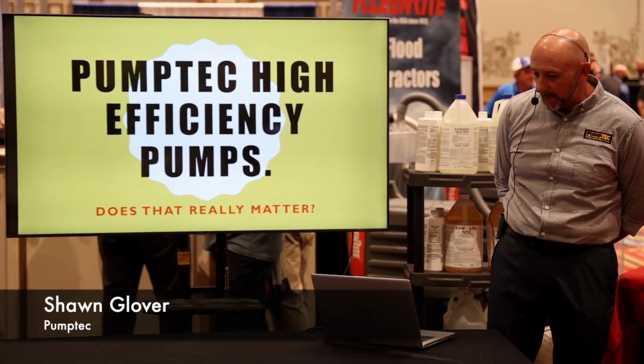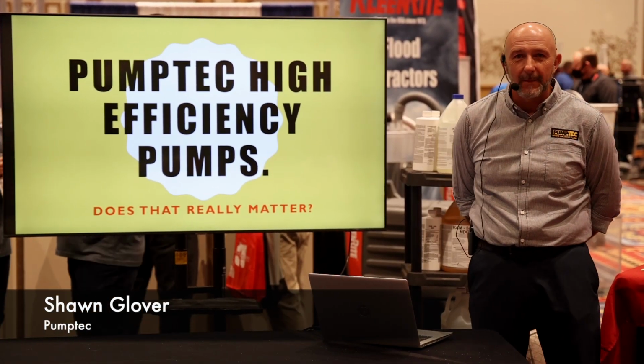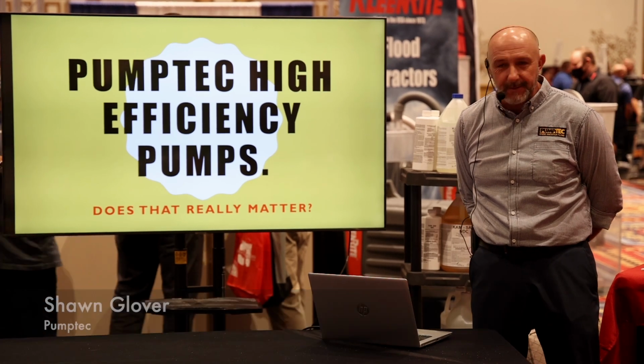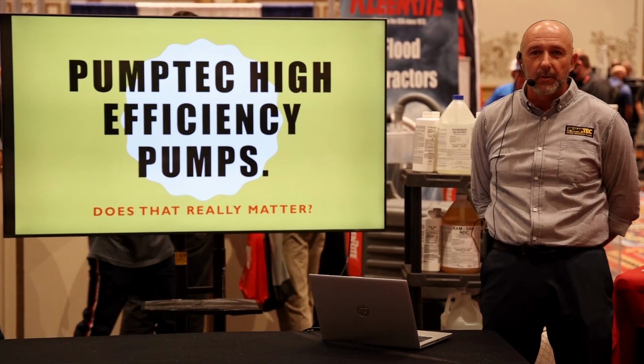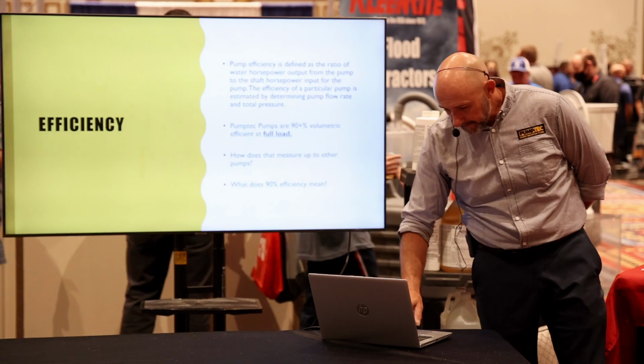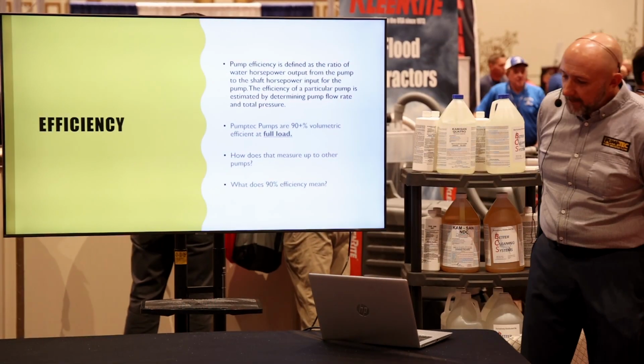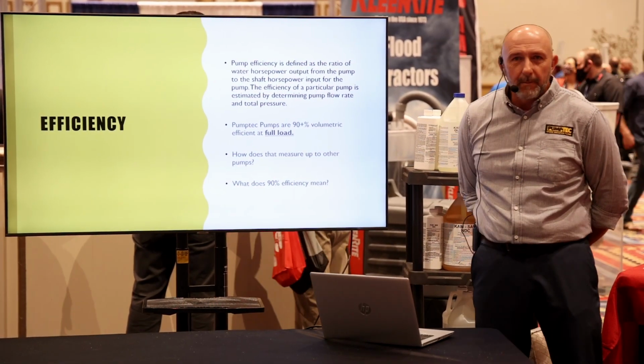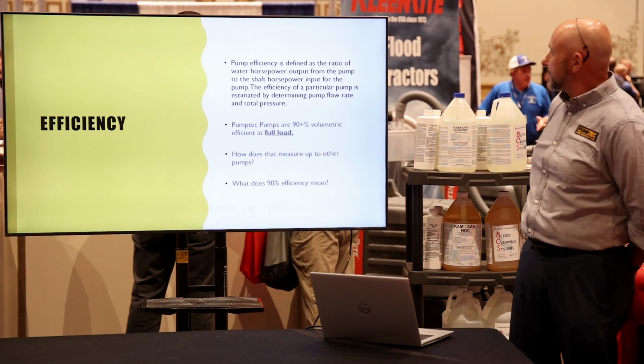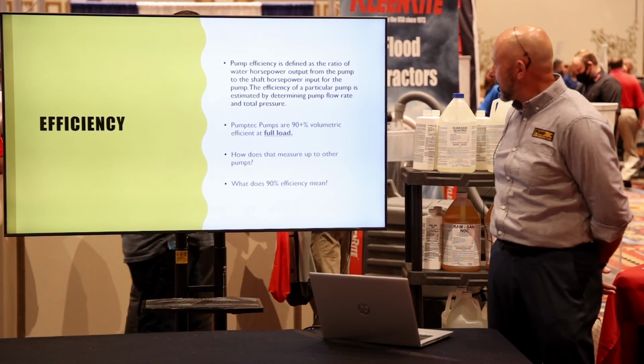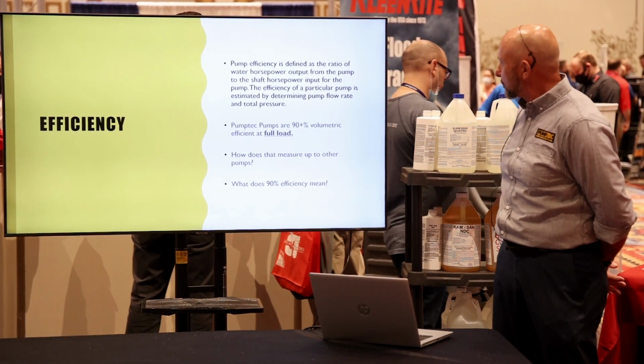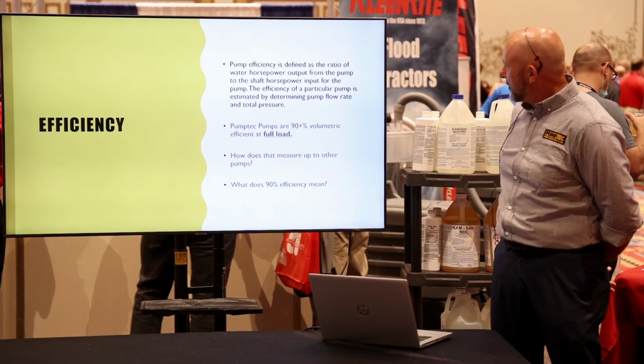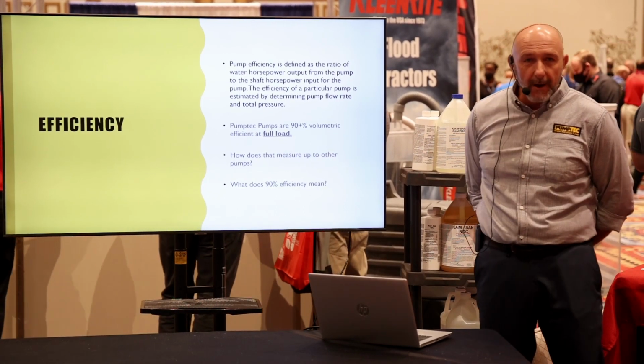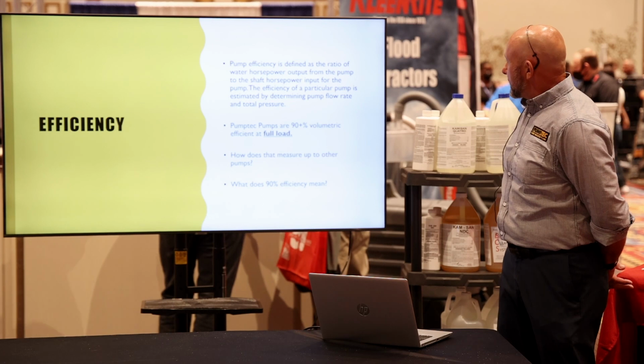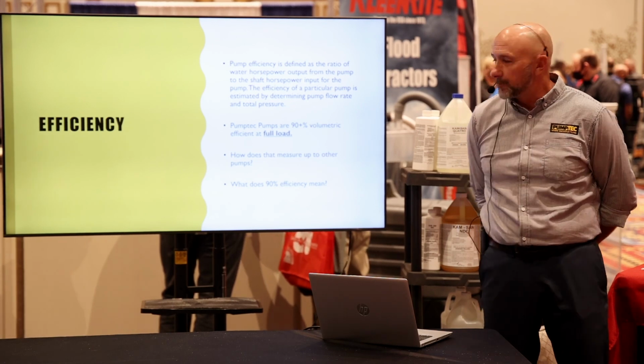I'm Shawn Glover with Pumptec, and today I want to talk about Pumptec high efficiency pumps and does efficiency really matter? So first off, let's talk a little about what is efficiency. The definition of pump efficiency is the ratio of water horsepower output from the pump to the shaft horsepower input for the pump. The efficiency of a particular pump is determined by the pump flow rate and the total head pressure.